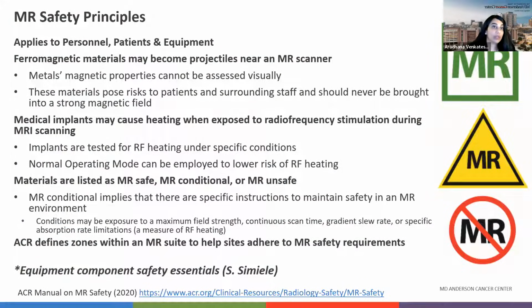And then a not insignificant point, in fact, this is vitally important, is to remember your MR safety principles when scanning and performing GYN brachytherapy in the MR suite. This applies to your personnel, patients, and equipment, as ferromagnetic materials may become projectiles near an MR scanner, and these could be subpart components of the actual procedural equipment inventory or something you didn't envision being brought into the vicinity by a member of support staff. So the vigilance of those monitoring the procedure is really of paramount importance.